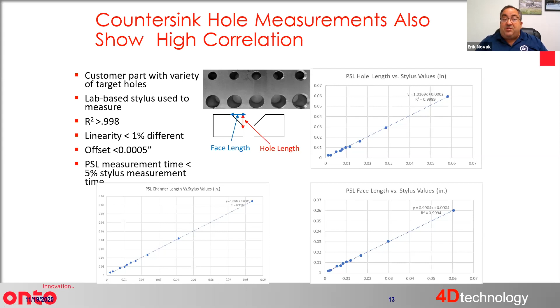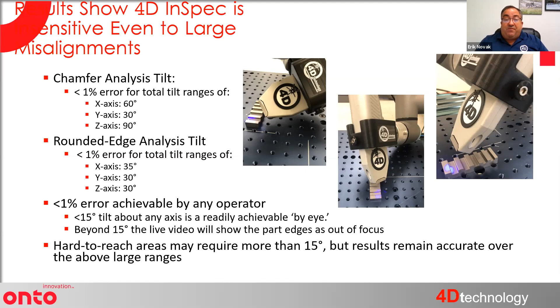And we're very insensitive with a three-dimensional technique to geometries. So if we think about misaligning our measurement system, so it's coming in at steep angles to a measurement part, or it's twisted, or as you see on the right, it's canted at another angle, you can actually be off in all cases by more than 30 degrees and actually have less than 1% error in your chamfer length, in your edge break radius, and things like that. And so less than 1% is very achievable by any operator. Just by eye, it's extremely easy to line things up within 15 degrees, even within 5 degrees. And beyond that, the live video we provide will actually show part edges as being out of focus.